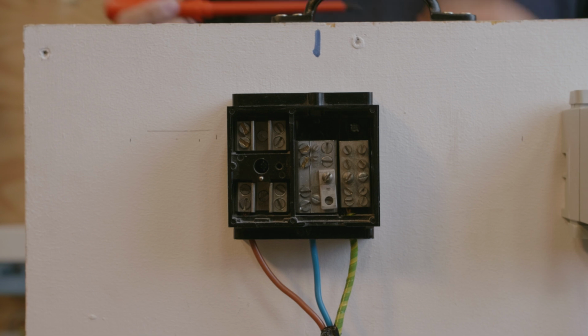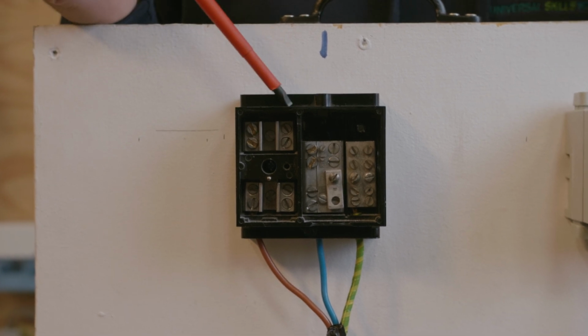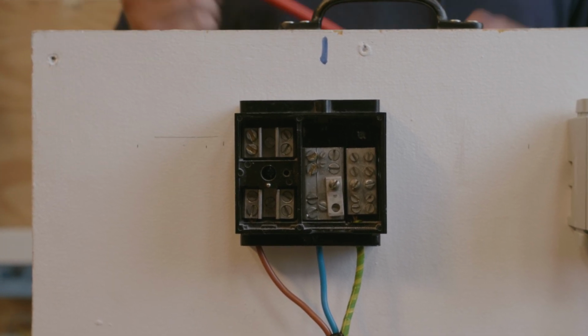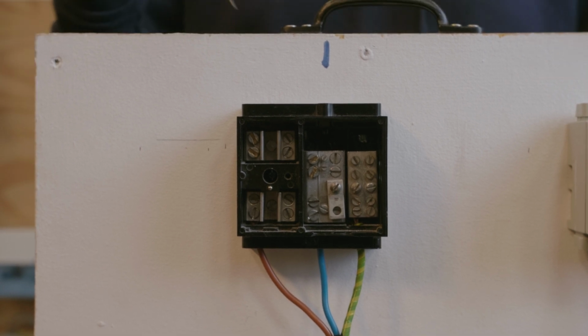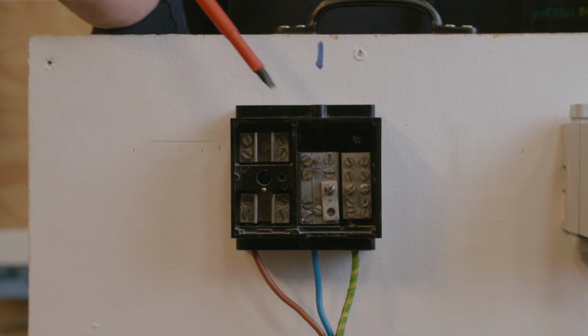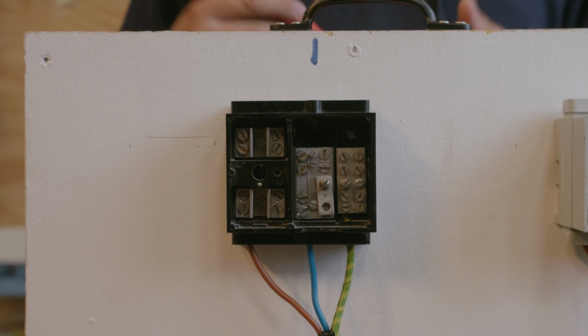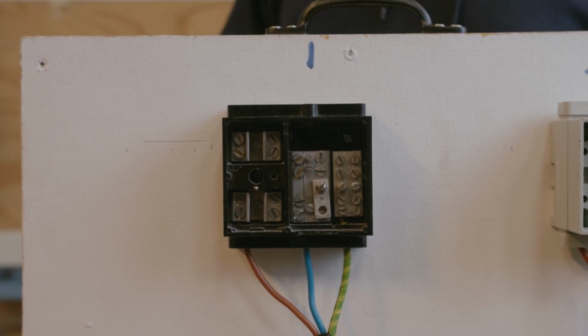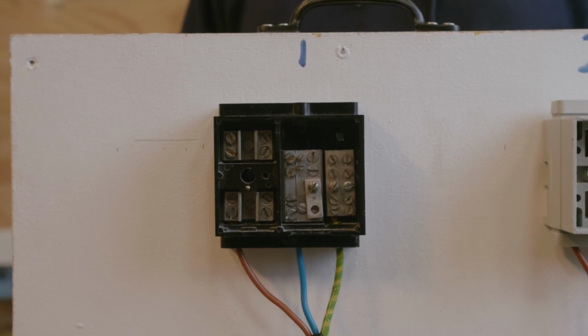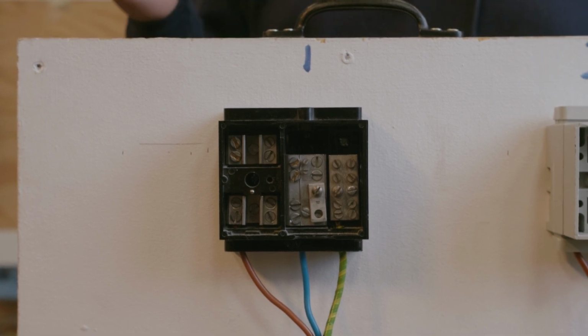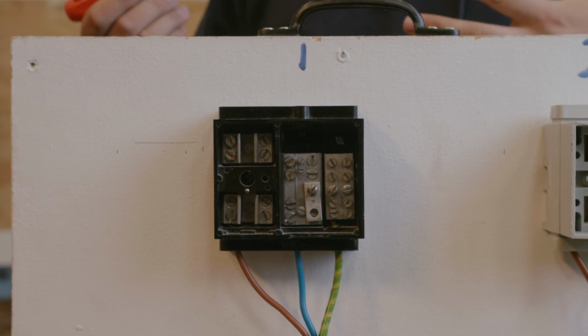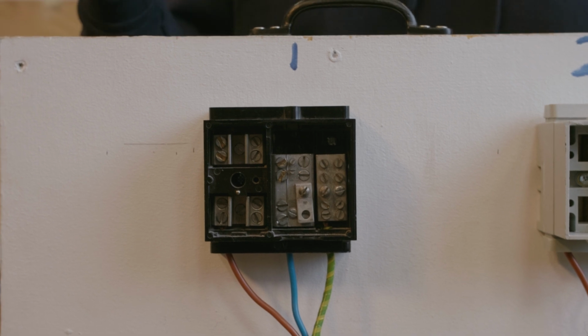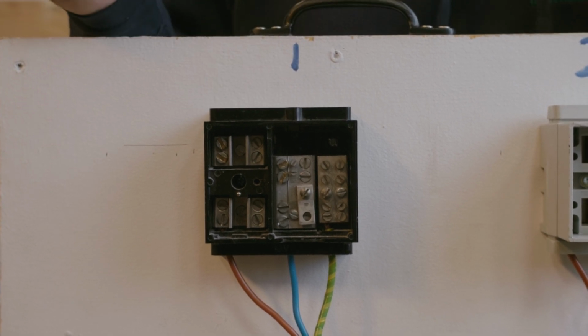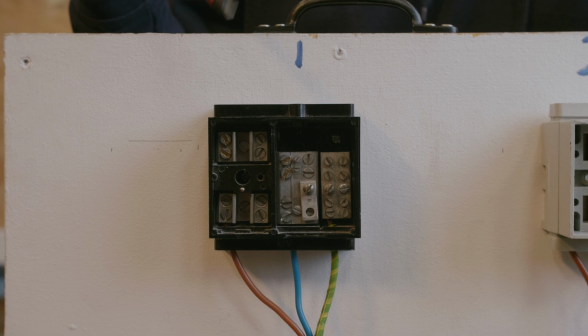So there's been a few problems with these type cutouts, allowing voltage along the actual material itself, so the cutout itself. So stray voltage can be picked up on this type of cutout. So most DNO, so distribution network operators, will be changing these. So it's something that you may want to look out for and just observe when you are doing the job, whatever that may be.